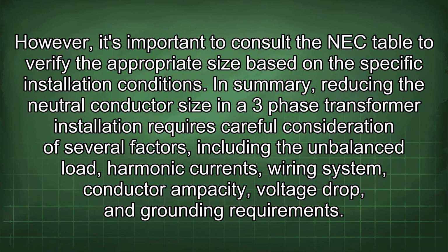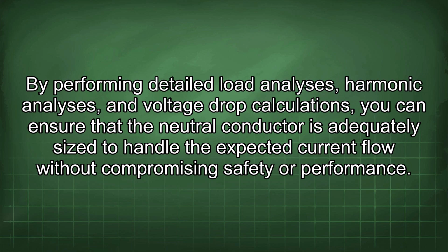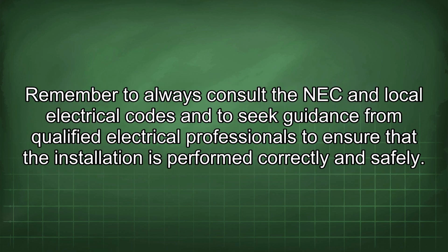In summary, reducing the neutral conductor size in a three-phase transformer installation requires careful consideration of several factors, including the imbalanced load, harmonic currents, wiring system, conductor ampacity, voltage drop, and grounding requirements. By performing detailed load analyses, harmonic analyses, and voltage drop calculations, you can ensure that the neutral conductor is adequately sized to handle the expected current flow without compromising safety or performance. Remember to always consult the NEC and local electrical codes and to seek guidance from qualified electrical professionals to ensure that the installation is performed correctly and safely.